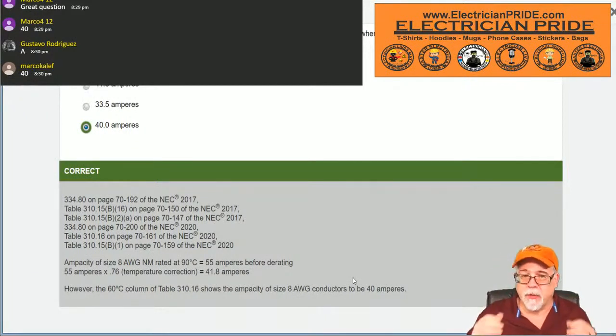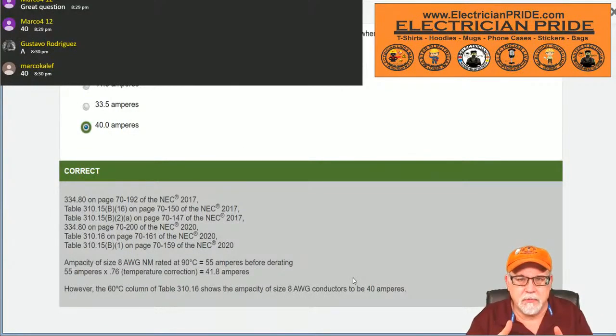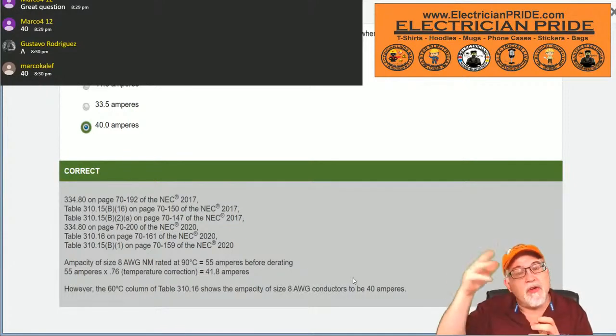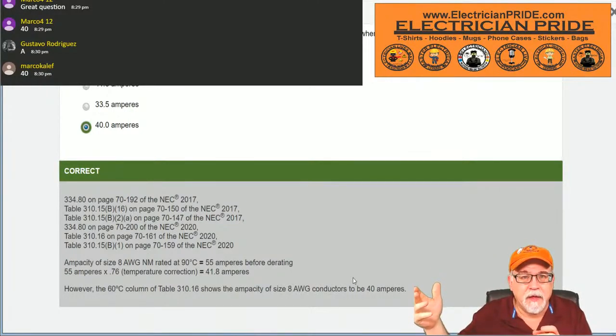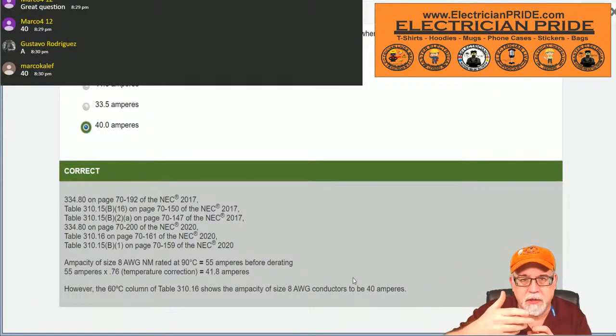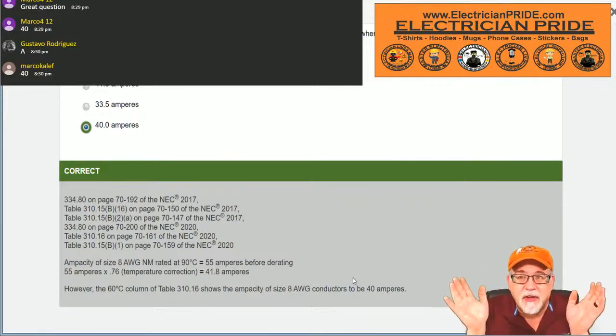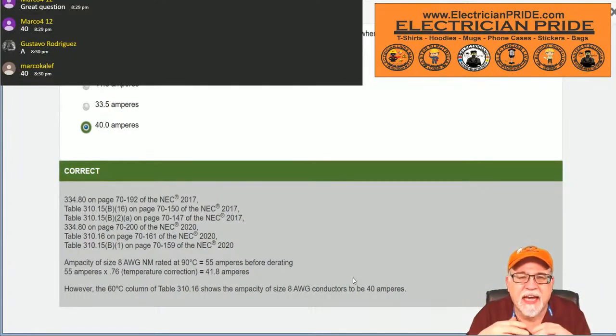So I make this simple for people. First thing you're always going to do is choose the right conductor to handle the load. If the terminals are 75-degree rated terminals, choose the value under 75. Then you can apply the value at the 90-degree for adjustment and corrections just to make sure you still have a conductor that is adequate to handle the load. Okay, and if it's higher than what's in the 75-degree column or in the 60-degree column, it's okay. That means it's still adequate to handle the load, but you can't load it up more than the value that's under the original column you chose, like the 75 or the 60. Okay, easy way to remember it.